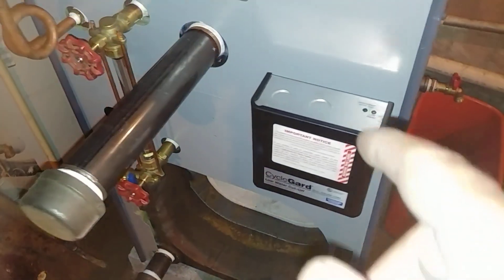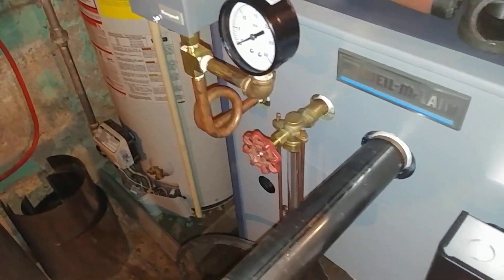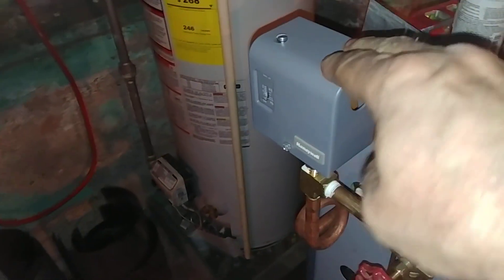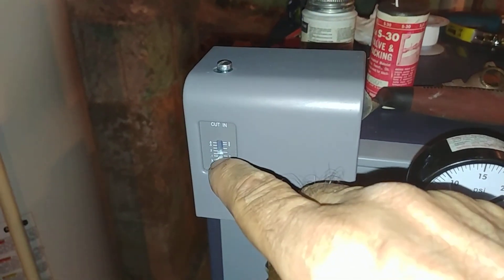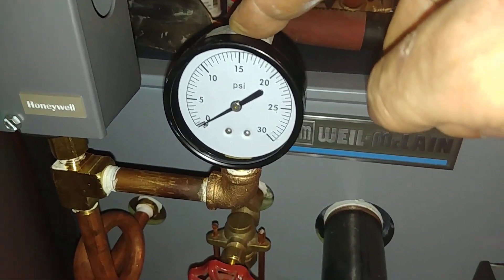It's holding water — you can hear the water heater firing away because we filled it with hot water. Hopefully that'll help dissolve some of the detergents in there. CycleGard is mounted, we've got the water heater shut off, our 270 pigtail Pressuretrol from stock. We turn it down even though it comes out of the box almost all the way to the top. We've got our pressure gauge here with the tester so you can take the pressure gauge off and blow in to test that the pigtail is clear.